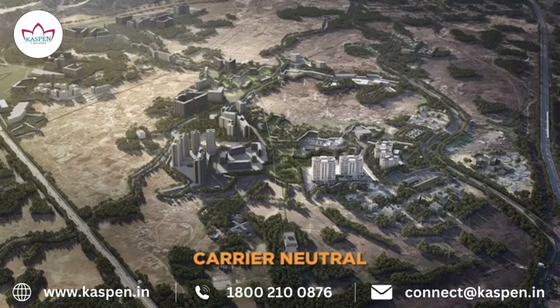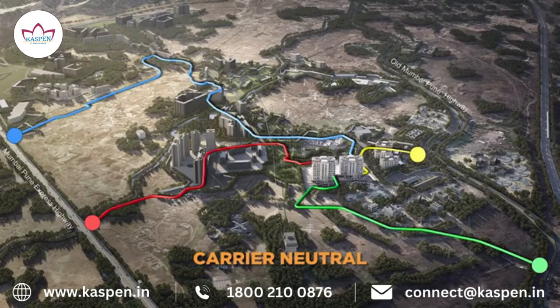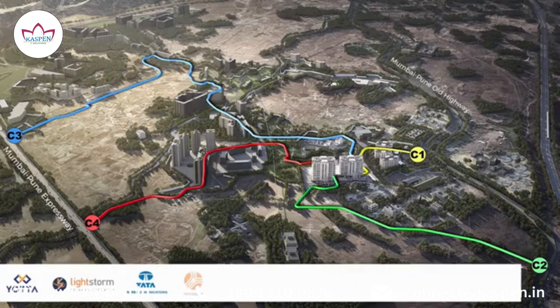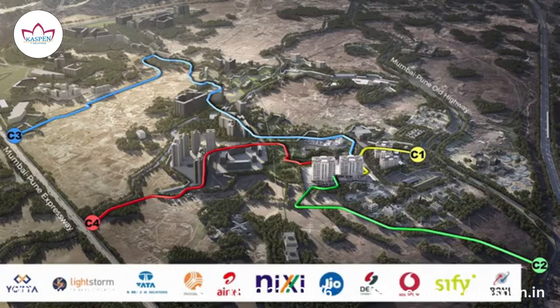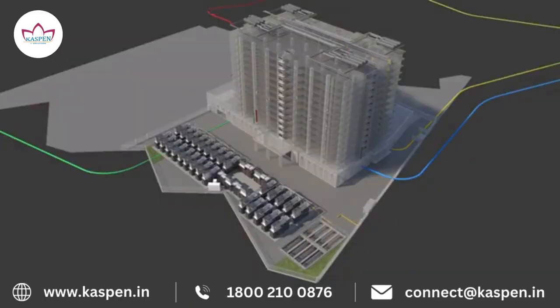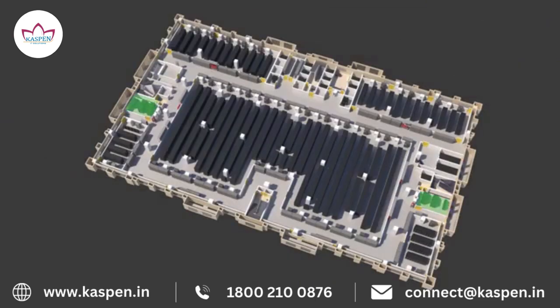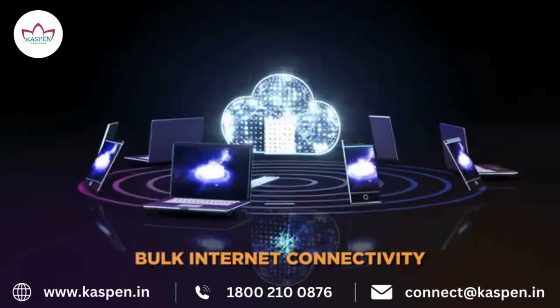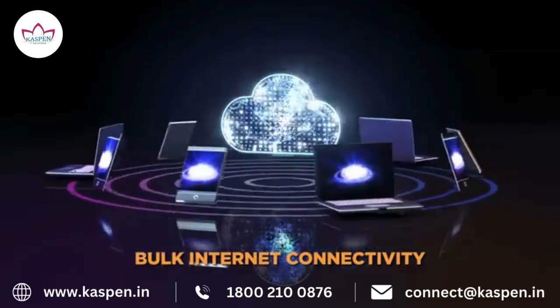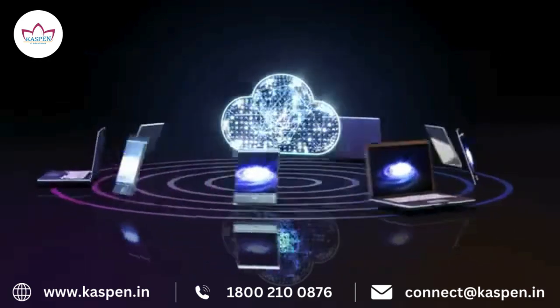Yotta NM1 is extremely well connected to the rest of the world through 4 captive and redundant telecom paths. All leading telecom operators have brought their fibers from these paths to the data center. These fiber cables rise on 2 sides of the building in independent conduits and terminate in redundant meet-me rooms, MMR, on 2 sides of the server hall floors. From meet-me rooms, we provide copper and fiber cross-connects to the customer racks through an array of redundant cable trays. As a Class A ISP licensee, Yotta also provides bulk internet connectivity to its hosted customers.